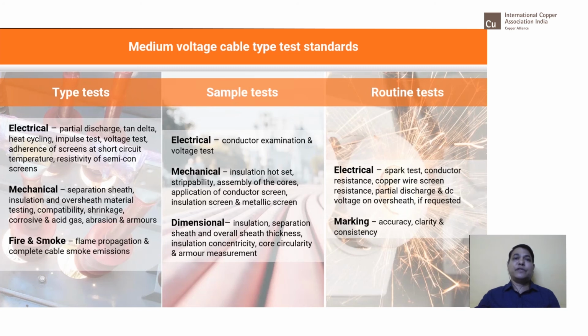What is the difference between the three types of test? In a type test, as you can see, there are a lot of electrical tests, which are partial discharge test, tan delta, heat cycling, impulse test, voltage test, adherence to short circuit test, and resistivity of semiconducting screen. Similarly, mechanical tests on the bedding or separation sheath, material insulation, and compatibility of the cable. When the whole cable is put into the oven for certain days, 14 days or 7 days, as per the standard, the material reaction between the components should not affect any quality of insulation or sheath in its mechanical properties. Hence, it is tested.